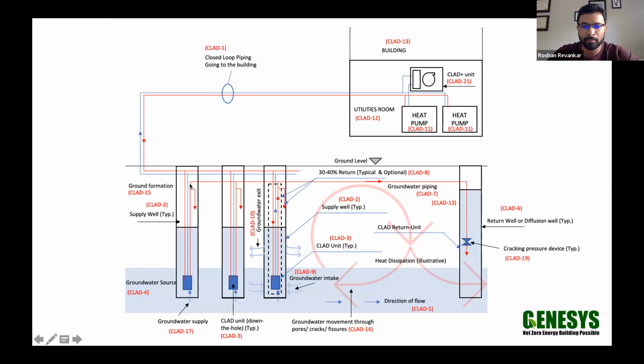So we talked about, I mentioned briefly, this cracking pressure device. This pressure device essentially holds pressure and only opens when there is flow or above a certain pressure limit. What that means is that this particular pump does not have to really do all of the work like a typical open loop pump, where it's got to pump through this entire system into a discharge well. The head really is essentially the difference of the water levels between the supply and the return, due to this particular device called the cracking pressure device.